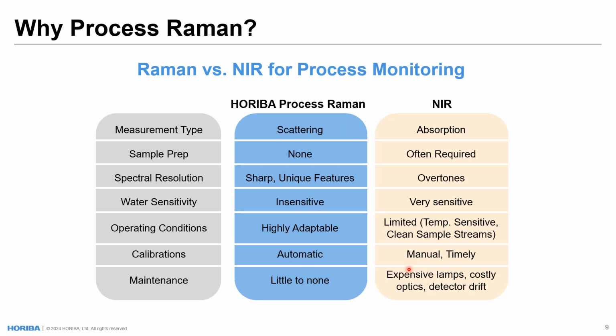That when a lamp is changed in the analyzer, that's expensive. It needs to be recalibrated that way. The optics are more costly, and also the detector is much more likely to drift over time with the sort of wear and tear of that instrument, where HORIBA Process Raman really has little to no maintenance, and I'll get into the history and the statistics on that a little bit later.